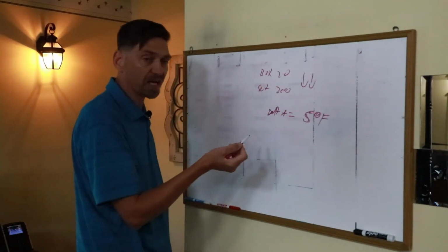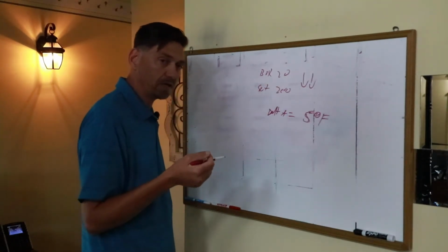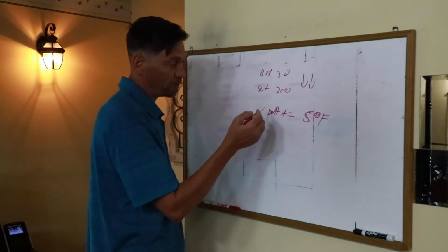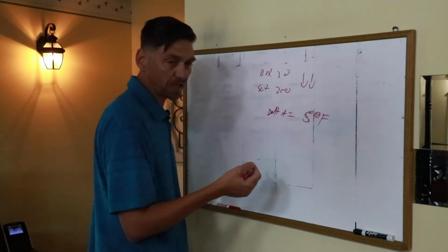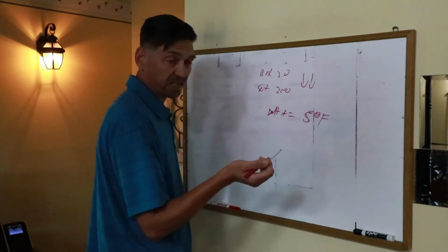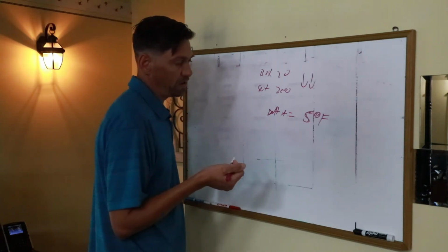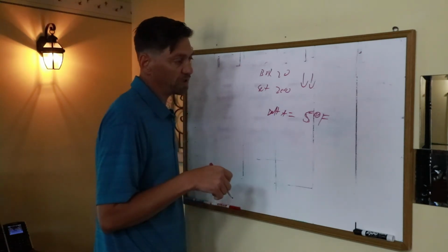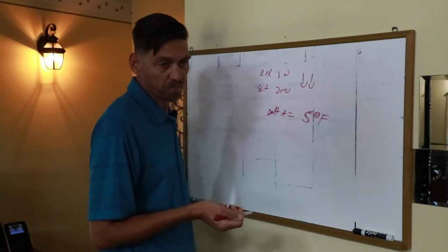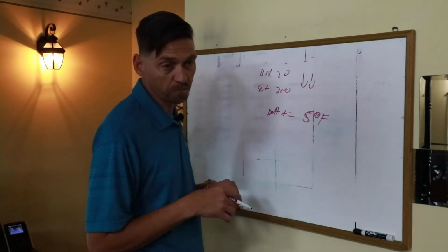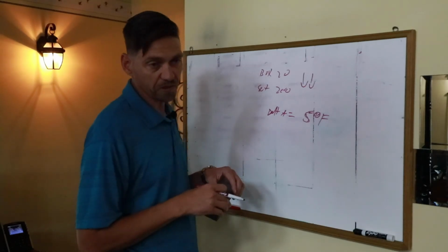If it's 20 degrees out of range and it's on high speed and it's pointing down that it's supposed to be cooling and it's not getting the job done, and you went in there and checked it all out and the delta T was 5 degrees, we're either out of Freon or we're froze up. These units work pretty good compared to units I had 20 years ago, so they really don't freeze up. But obviously if the coils are all froze up, the suction pressures go through the roof and it won't cool. But that tells you if the unit's working or not.